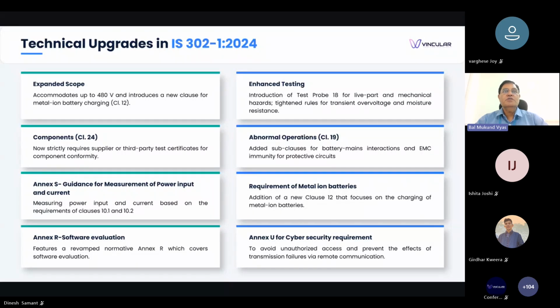So Annexure R focuses on demonstrating that the software development process and system architecture of the software are robust enough to maintain safety. And so it is important that the software itself is reviewed to ensure that it is fault tolerant. There is proper error detection. The safe state behavior is properly defined, and it is verified and validated for the safety aspect. Annexure R encourages mechanisms such as watchdog timers, memory checks, communication checks, data integrity monitoring, processor self-diagnostic features, and these measures help identify software or hardware malfunctions before they can create a safety hazard.